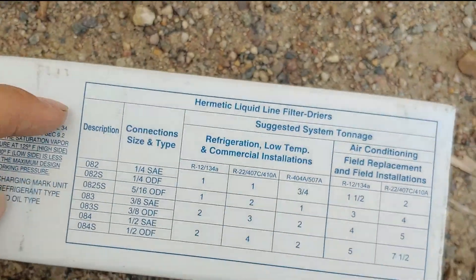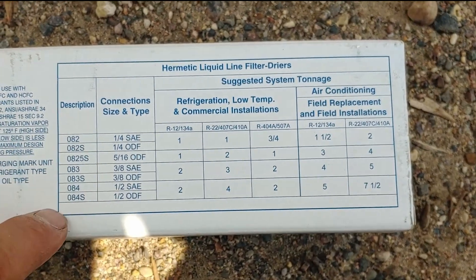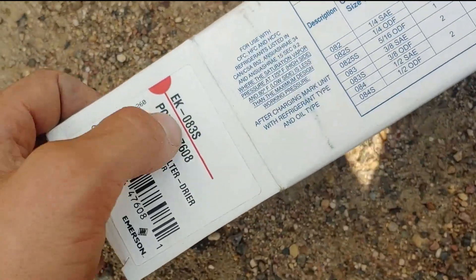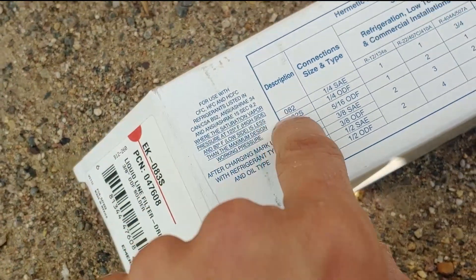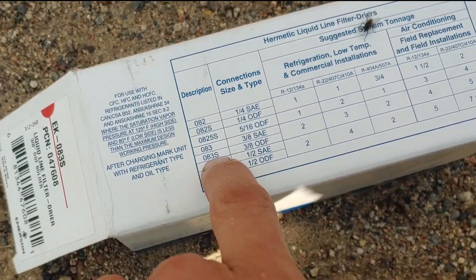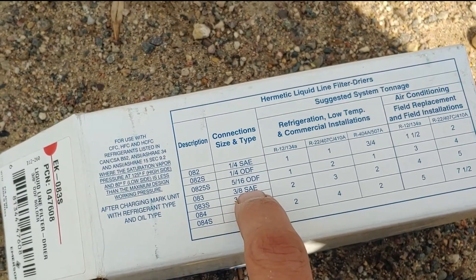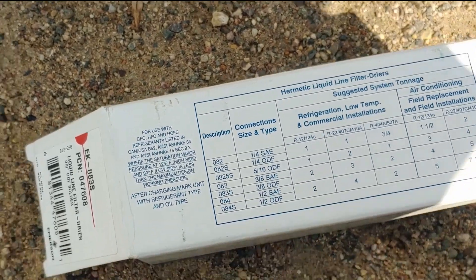They should have a chart on there that has your model listed. So this is the chart — they have all the different models listed. What you do is find your model, which is again our 083S, right there. Then we're going to follow this column down: 3/8 ODF, which is solder. They also have SAE, which is threads.